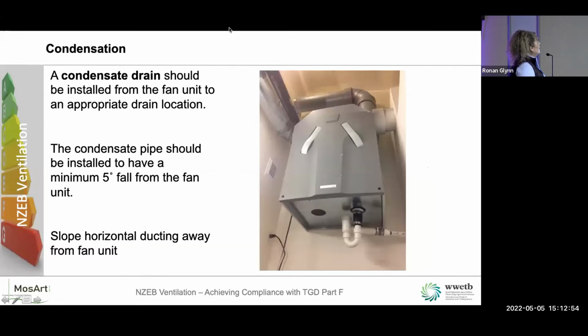So a condensate drain is really important. We've got hot and cold hitting each other, so we're going to have condensation. We've lots of vapor-laden air coming from our wet rooms, steam from showers and kitchens and stuff like that. So the condensate drain should be installed from the fan unit to an appropriate drain location. Okay, so that needs to go to the outside. You need your little U-bend on it because you don't want any back gas. So if you put that in a waste drain and there's any smells coming up, it'll come back up and end up in your supply rooms. So you need to have your little U-bend.